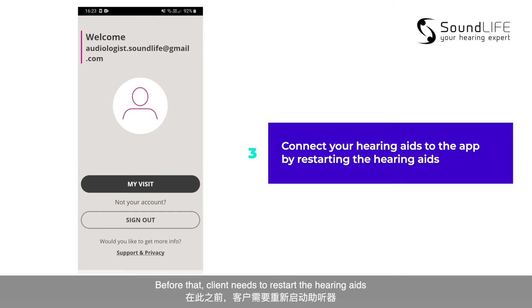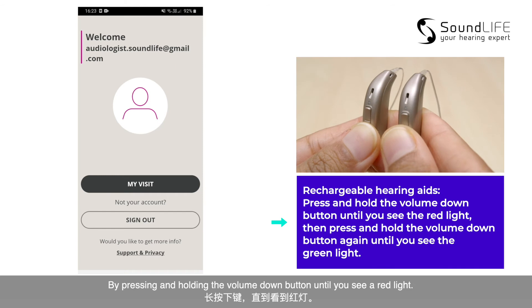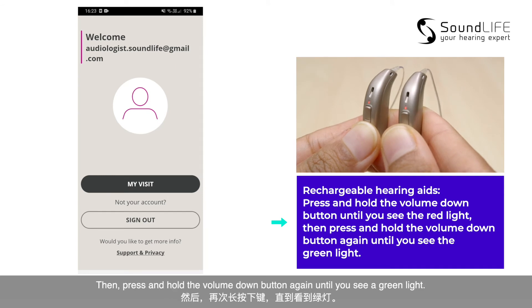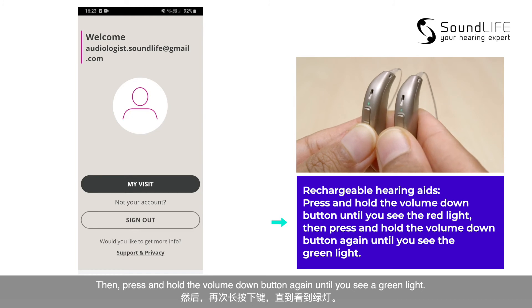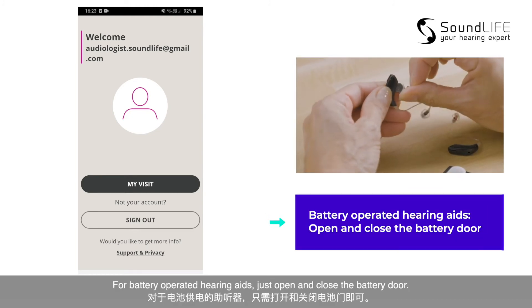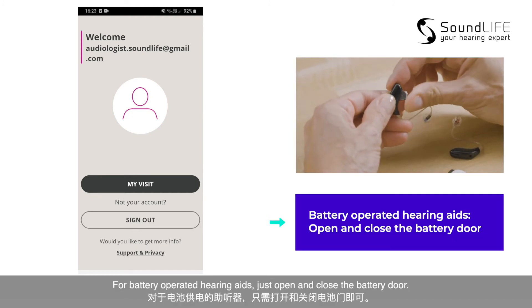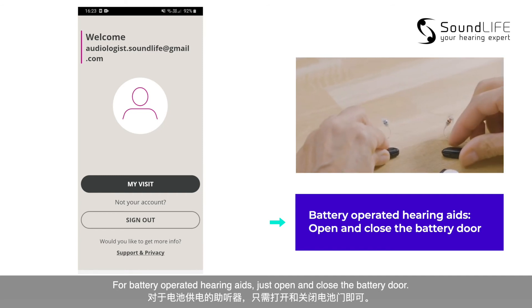Before that, the client needs to restart the hearing aids by pressing and holding the volume button until you see a red light, then press and hold the volume down button until you see a green light. For battery operated hearing aids, just open and close the battery door.